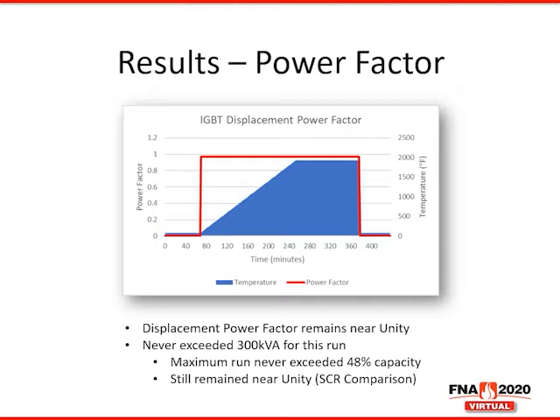If you were to compare this to phase angle control, as the power drops down and we go to a lower set point, you would see a lower power factor, let's say in this plateau phase, because power is being delivered inefficiently. One thing I want to point out too is that we matched our system to the 645 kVA VRT. During this cycle, our system never exceeded 300 kVA. So at its maximum point, it was still 48% of the total capacity of our IGBT MFDC power supply. And even at these lower set points, it was lower than that. The take-home point is that our power supply has a very good displacement power factor at practically any set point.